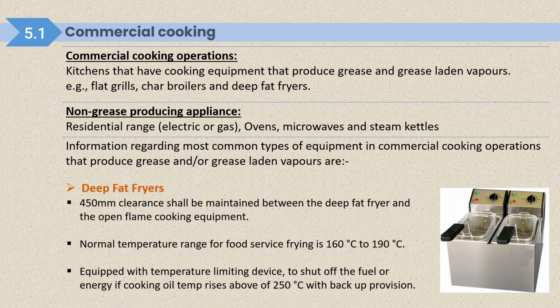So there are some guidelines given about the deep fat fryers. 450 mm clearance shall be maintained between the deep fat fryer and the open flame cooking equipment that we already discussed in the previous slide. The normal temperature range for food service frying is 160 degrees centigrade to 190 degrees centigrade, equipped with a temperature limiting device to shut off the fuel or energy if the cooking oil temperature rises above 250 degrees centigrade. So if the oil temperature is rising above 250 degrees centigrade, it will get shut off. It should get shut off with backup provision, like the limit control switch that we talked about in the previous slide.